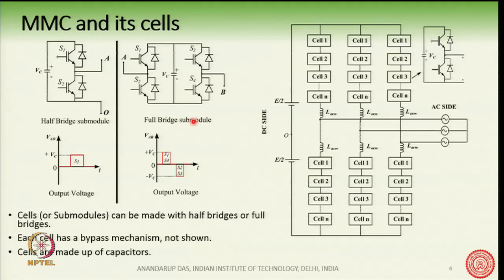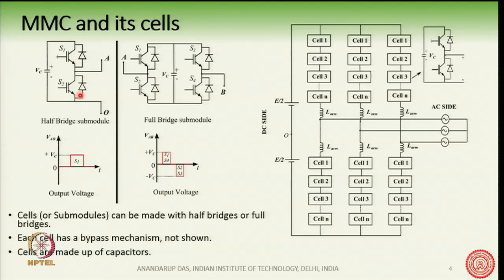The half-bridge sub-module is one possible variant of the cell structure, and the full-bridge is another. In the case of a half-bridge cell, there are two IGBTs which are complementary in nature — otherwise it would short the DC bus. The DC bus is formed by a capacitor, so there is only one capacitor and no isolated DC source connected to the DC bus of this cell.